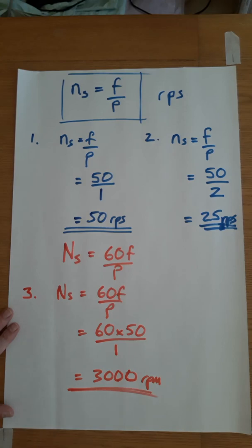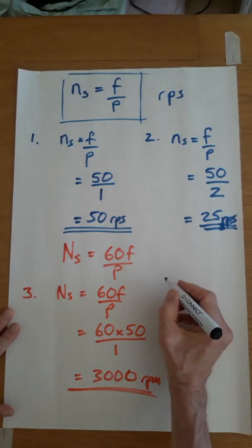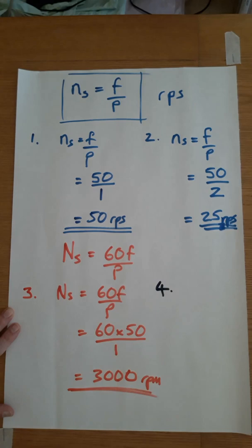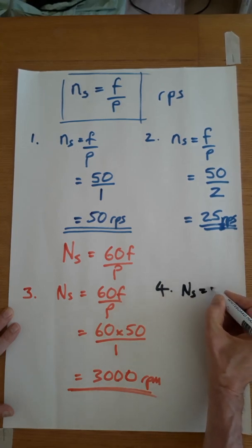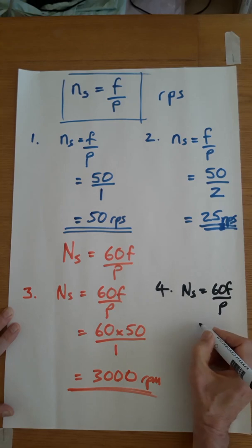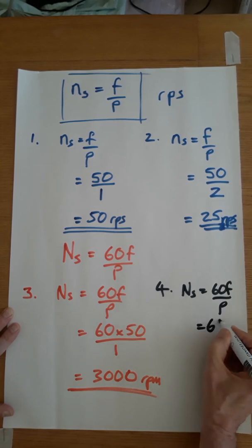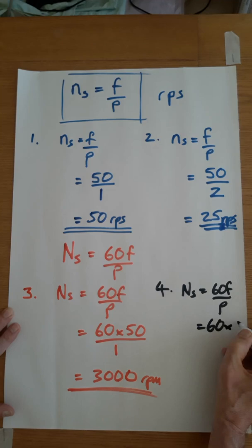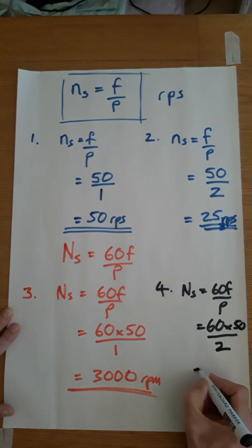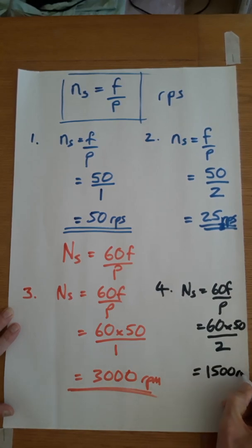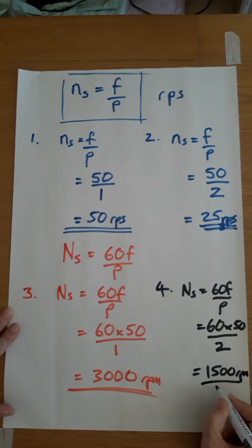Example four: a four pole machine on 50 hertz. Ns = 60f over p — 60 times 50 over two pairs — and that gives you 1500 rpm.